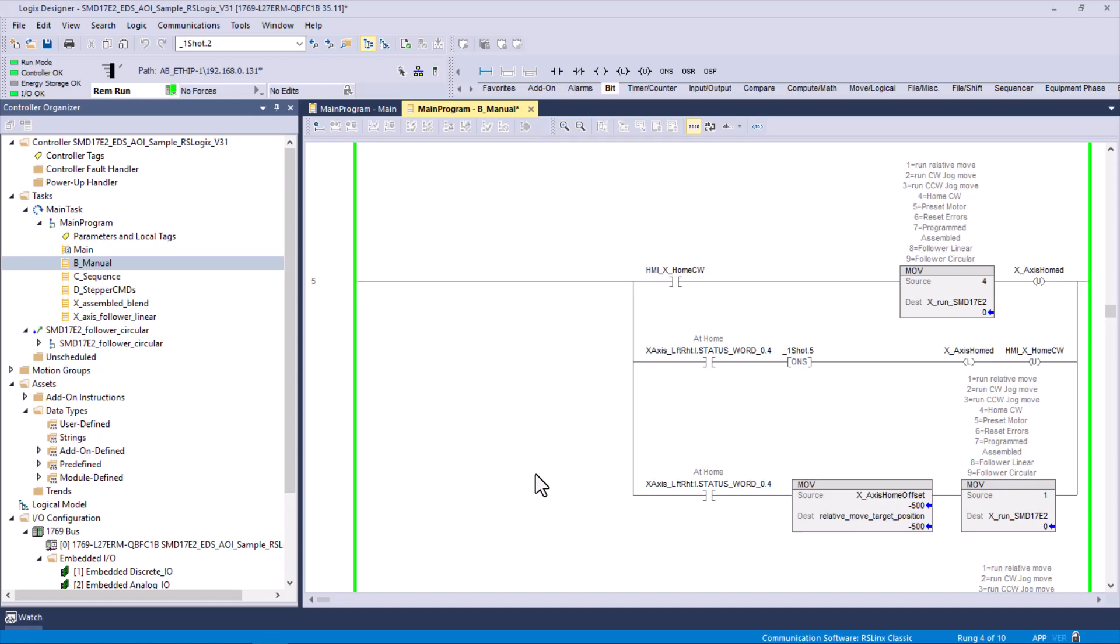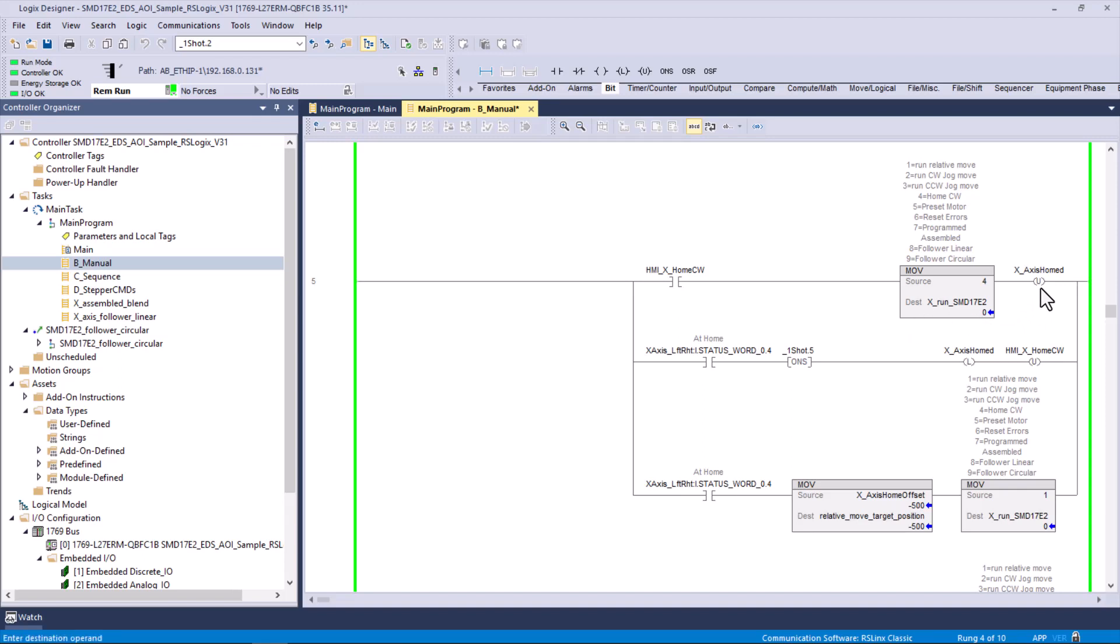In this rung logic, and there's many ways you can do this. Typically, when I'm just exploring with a piece of hardware like this, I don't do a lot of deep analysis on how I want to write the code. I just throw something in there and then tweak it until it does what I want. If I was doing this for a customer, I would make sure it fit their standard operating procedure or their conventions. If I toggle this bit on, it moves a 4 in there and it untoggles this axis homed. If I put a 4 in, I could do that right now, but I see that my axis is at the far end. I don't want to wait for it to home.